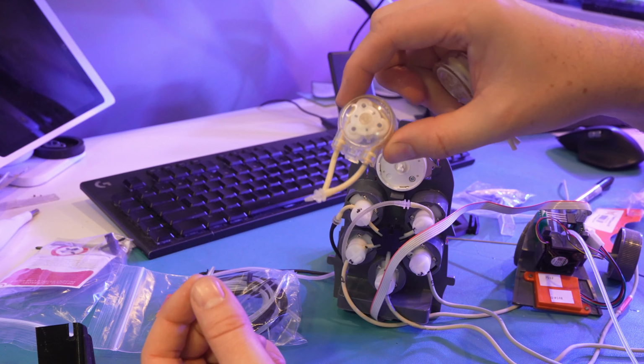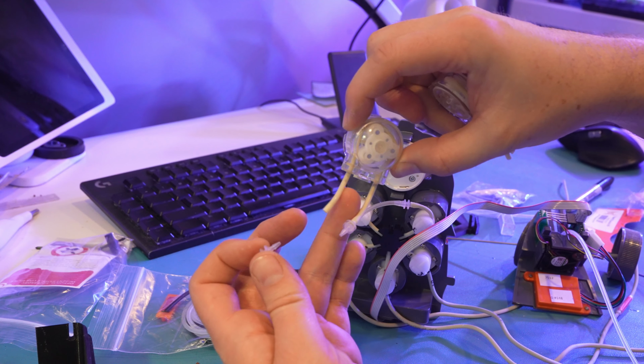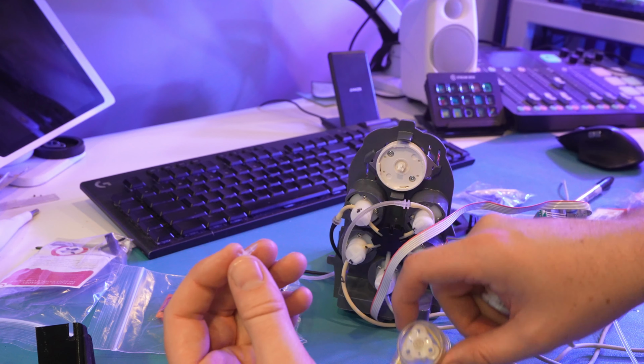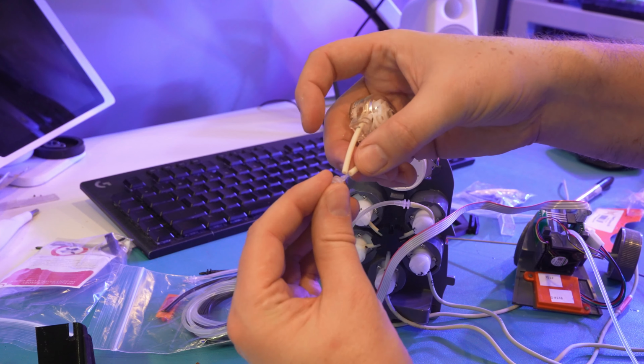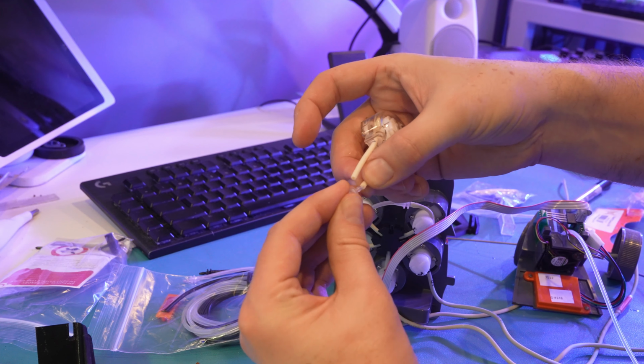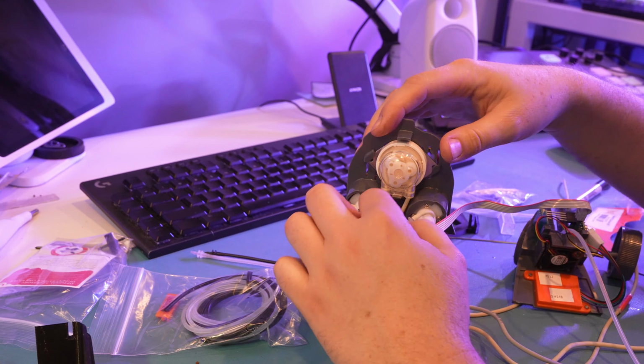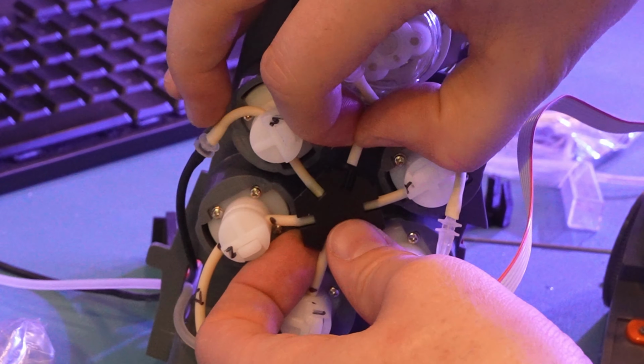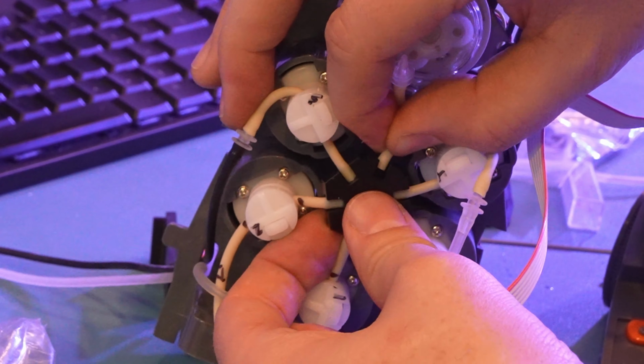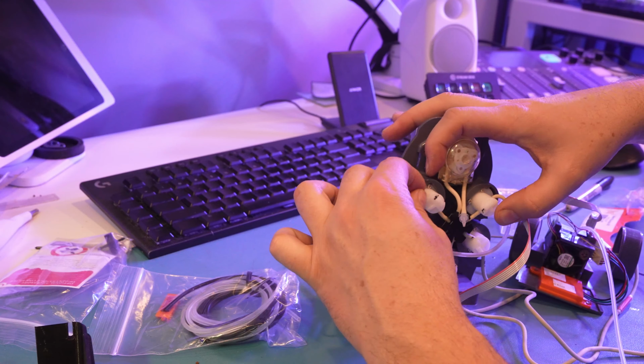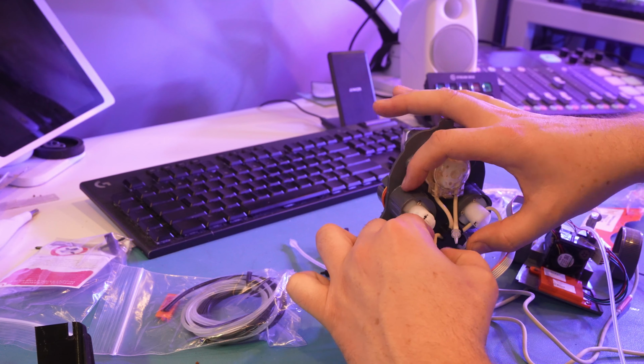So taking a look at the old pump head, the left was on 12 o'clock on the manual and the right-hand side had our little connector. So I'm going to just put this on the right-hand side just to prevent any confusion later. There you go, so new pump head's in place, and reconnect this guy to our 12 o'clock. Okay, now next we're going to replace the waste line, so I'm going to pull this one off.